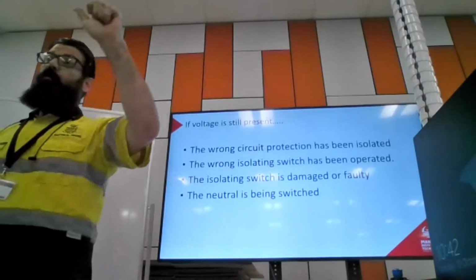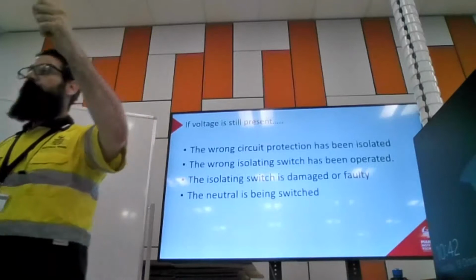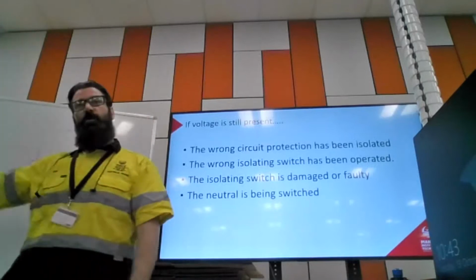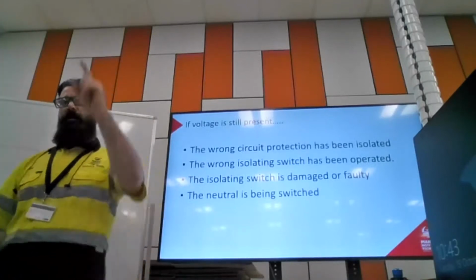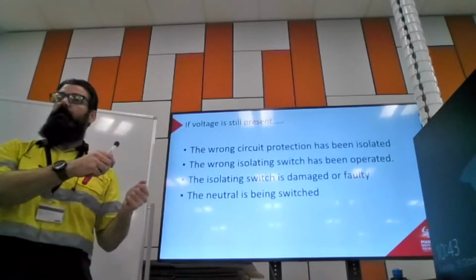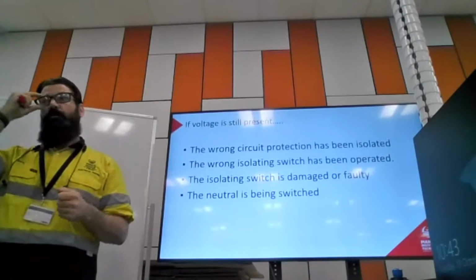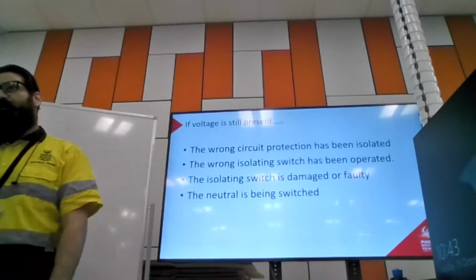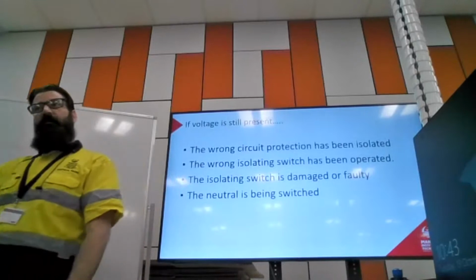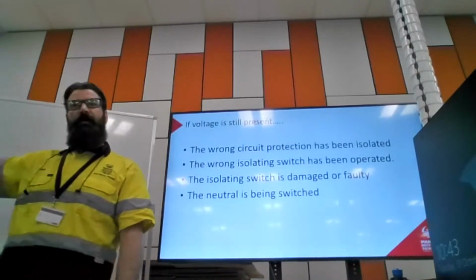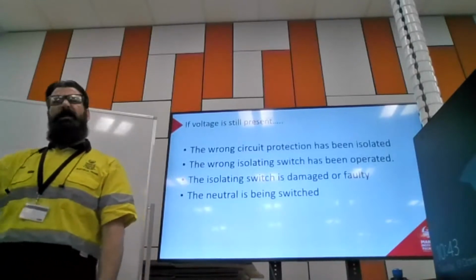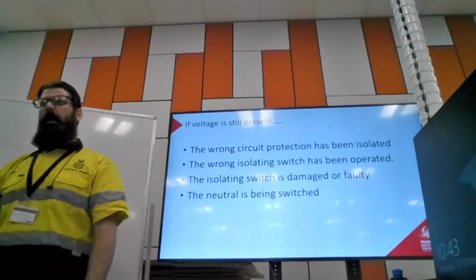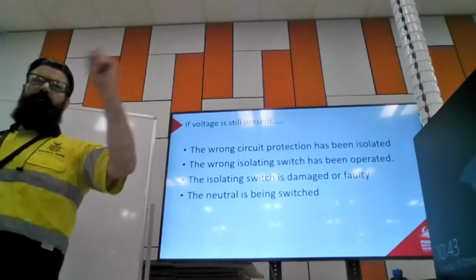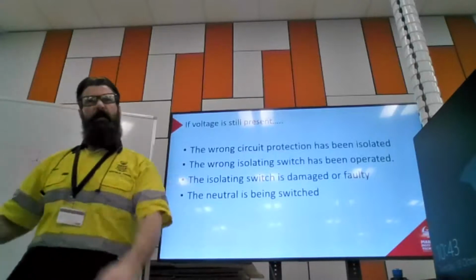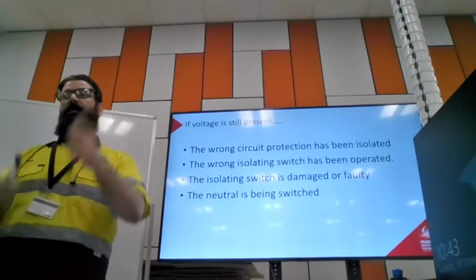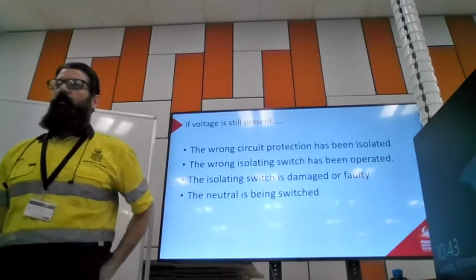It wasn't until somebody came to work on one of them, switched one of them off, that it broke the neutral on a different piece of equipment. So the one that he was working on still looked like it was isolated, even though the neutral was still connected through the switch that was still on. But then they started having issues on the other equipment that they weren't working on. Somebody started complaining, have you guys switched this off? I went, no, we only switched this one off. And so, oh, this one's not working now. So they went to investigate that, not realizing that they'd switched the neutral for that one.